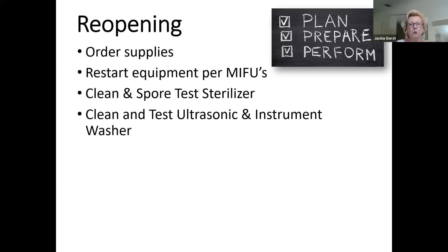You've got to fill your ultrasonic instrument cleaner or instrument washer, get them prepared for use, and then test. You all know how to test an ultrasonic cleaner with the aluminum foil test: hold foil in there for 20 to 30 seconds, pull it out, and it should be uniformly pimpled or dimpled with holes. If it comes out shiny, your ultrasonic is making noise, but it isn't sonicating—it's not imploding the bubbles and cleaning the instruments.